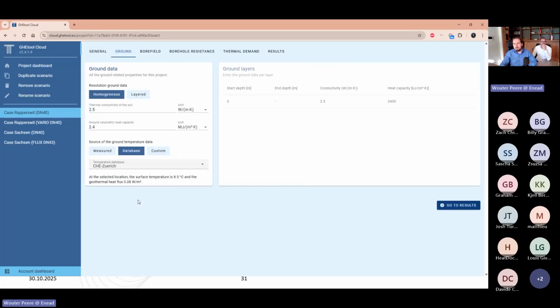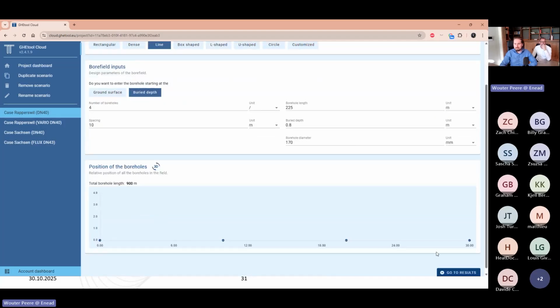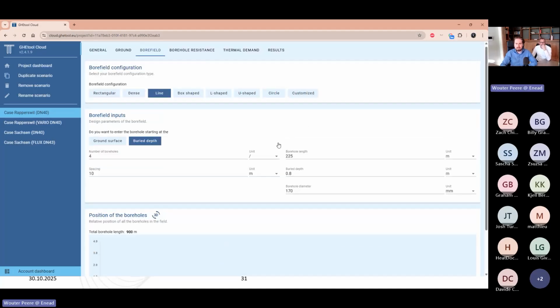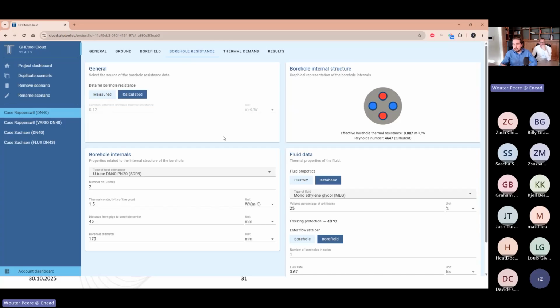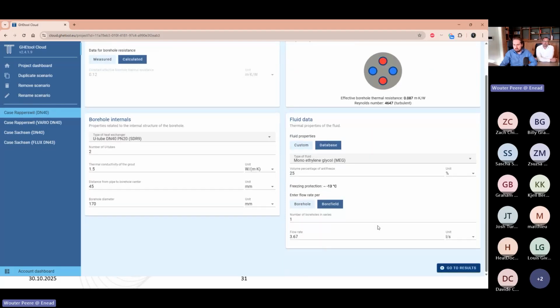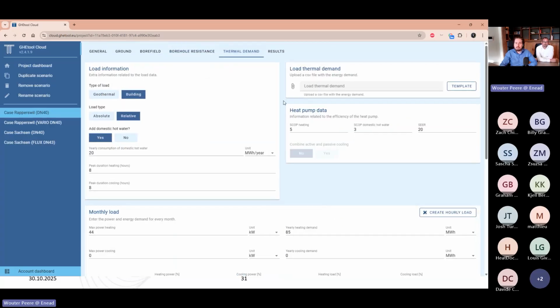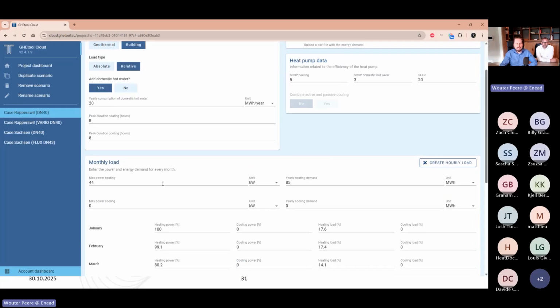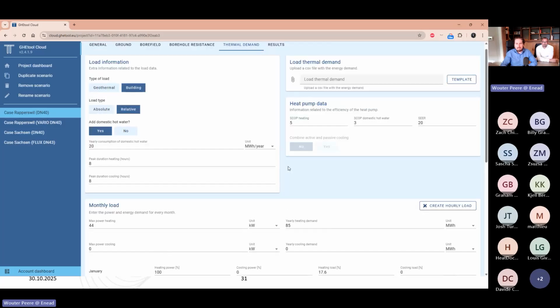The ground properties, it was close to Zurich, so we used these values. For the borefield, it was just everything in one line with 225 meters, as Sasha told you. For the borehole resistance, our first case is our traditional DN40 PN20 probe, an SDR of 9, with monoethylene glycol and a certain flow rate. For thermal demand, just to show that everything was right, a certain power, and then a certain energy demand as well.